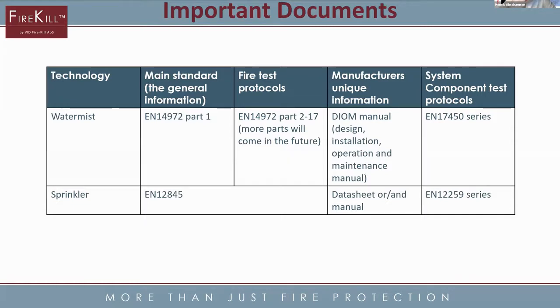Then you have the fire test protocols coming in parts 2 to 17, and more parts will probably be added in the future. Then you have the manufacturer's unique information, which is the DIOM. All Watermist is performance based, so every manufacturer has their own systems. That means there's no comparison between systems because they work differently — different pressures, flows, spacings, and so on — all found through full scale fire testing. Then you also have system component protocols that will come out later.